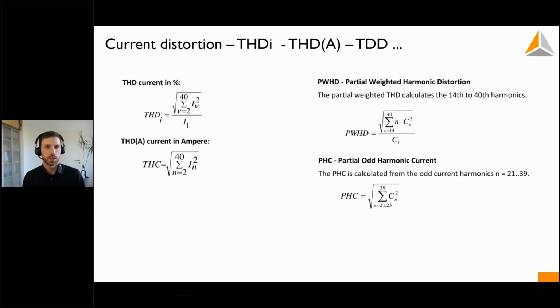This considers, for example, harmonics from the 14th order up to the 40th order. Each individual harmonic is multiplied with its order, this is the n. So the higher the harmonic order, the more it affects my value, because the higher the harmonics, the more harm they could possibly cause. And then there's another exotic value like the PHC, the partial odd harmonic current. This only considers odd harmonics from the order of 21 to 39, for example.